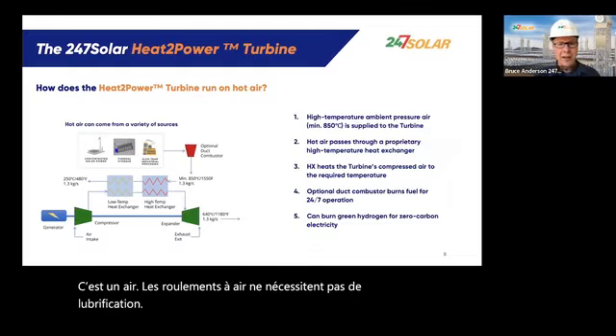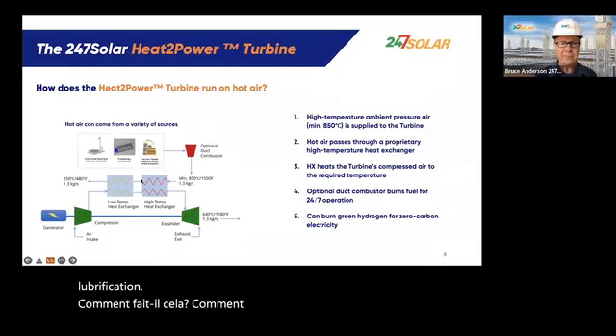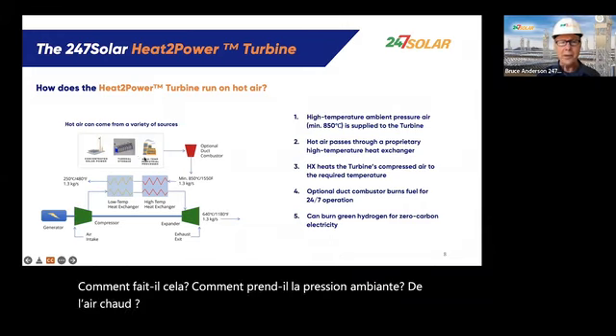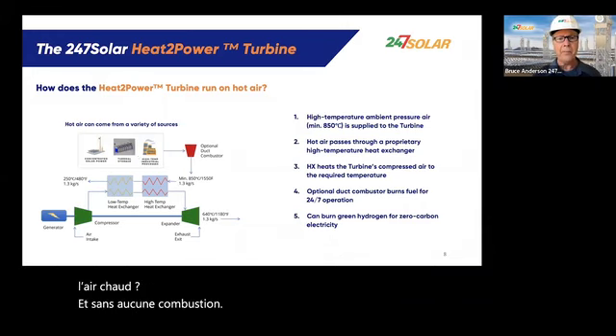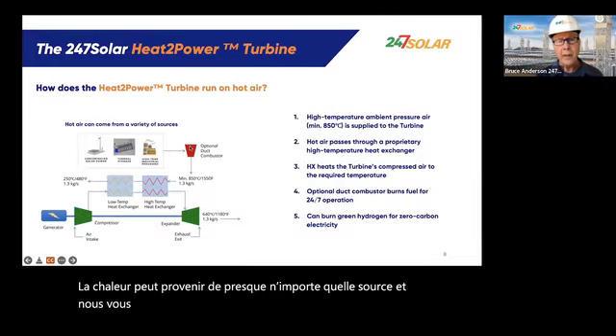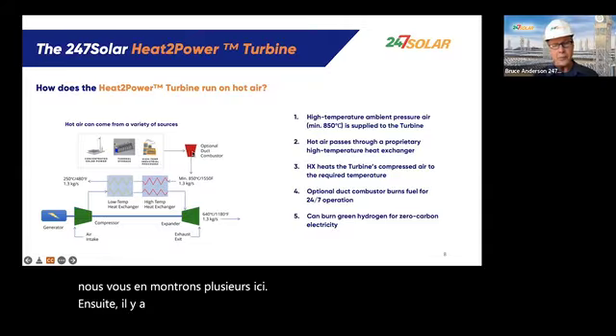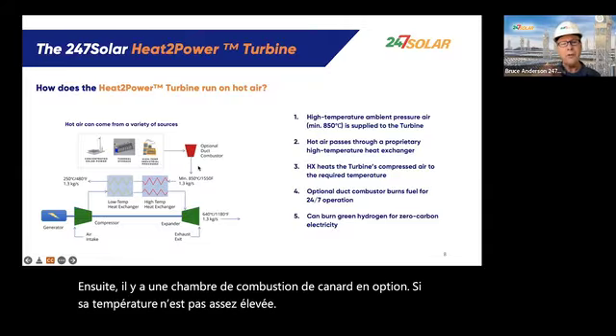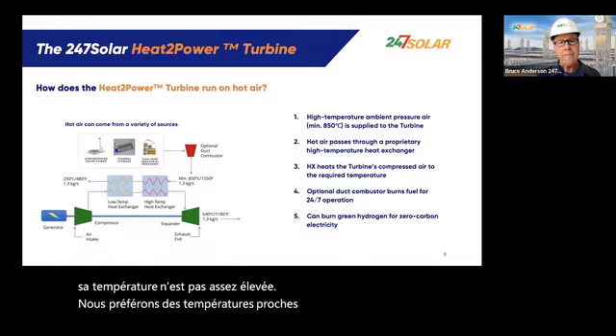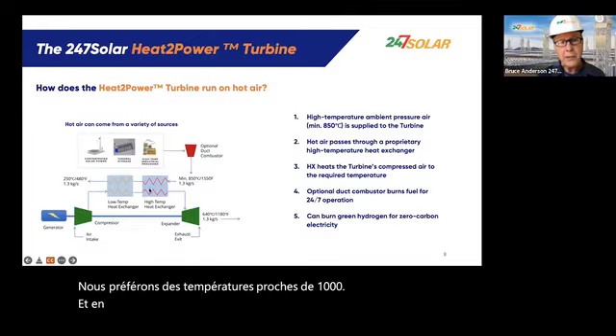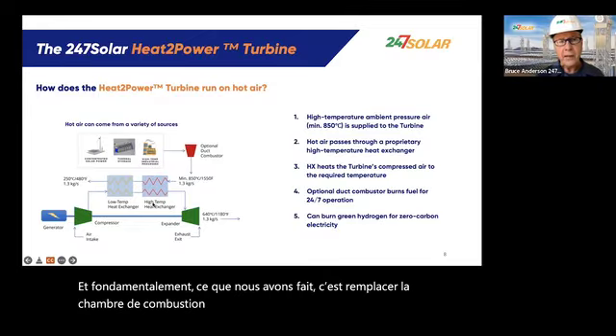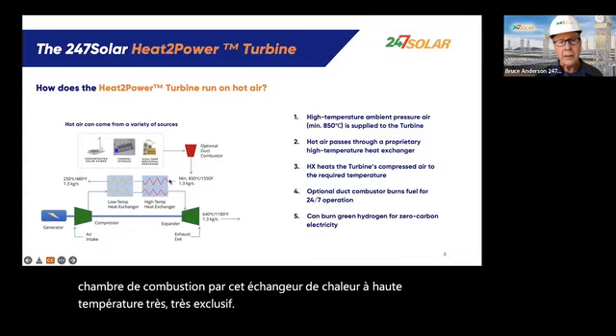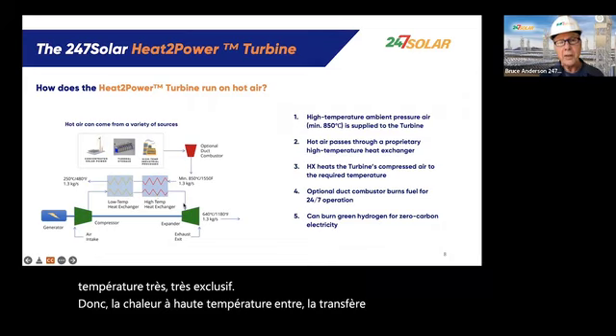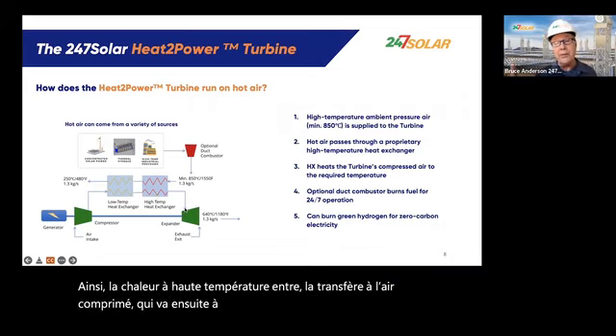How does it do that? How does it take ambient pressure hot air and, without any combustion, produce power? Well, the heat can come from almost any source, and we show you several here. There's also an optional duct combustor if the temperature is not high enough - we prefer temperatures approaching 1,000. Basically what we've done is replace the combustor with a very proprietary high temperature heat exchanger. The high temperature heat comes in, transfers it to the compressed air, which then goes to the turbine, exactly what a combustor does.